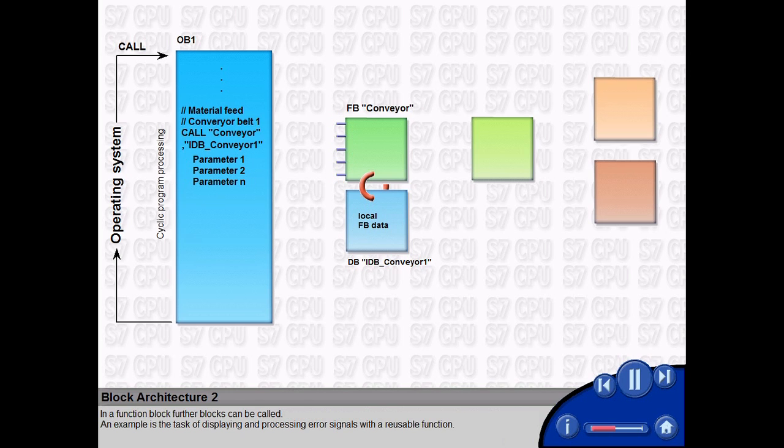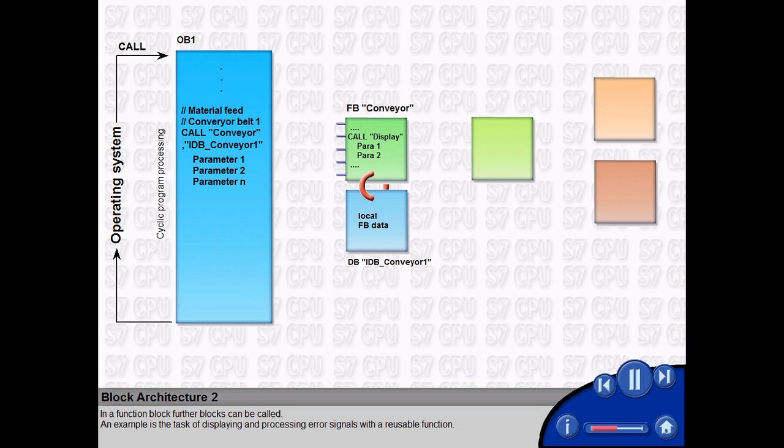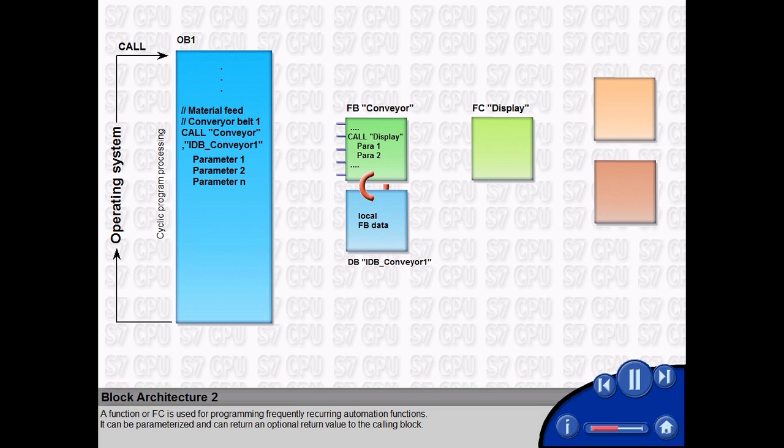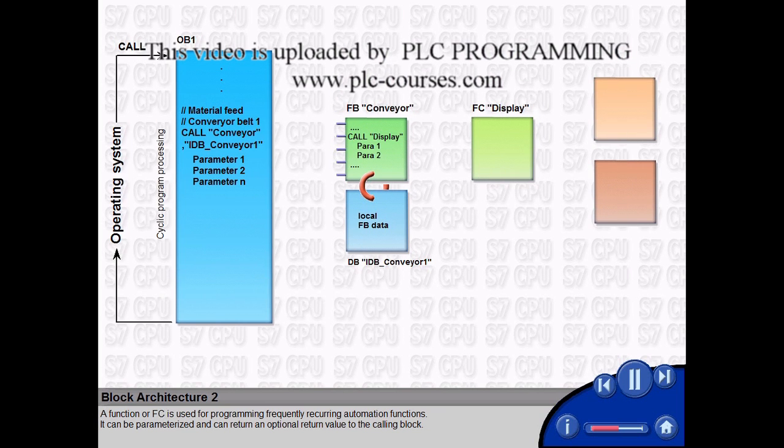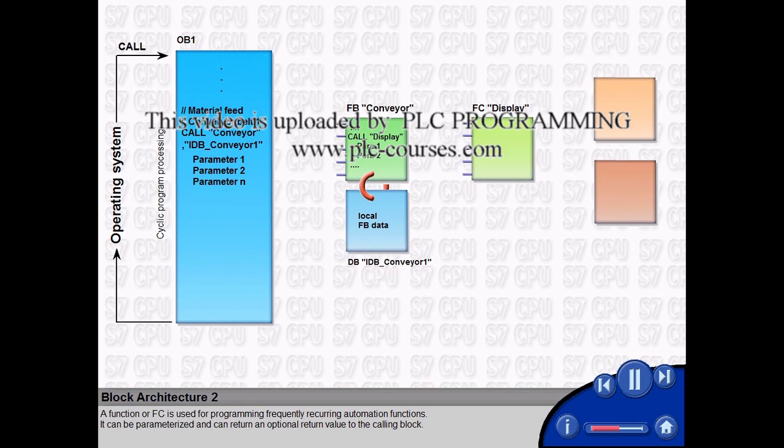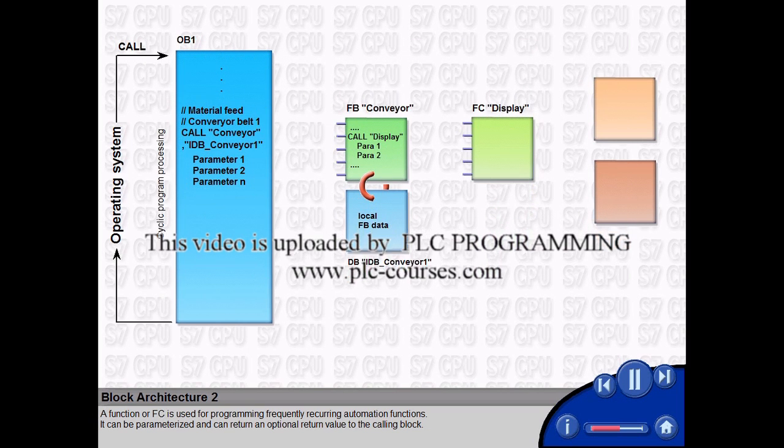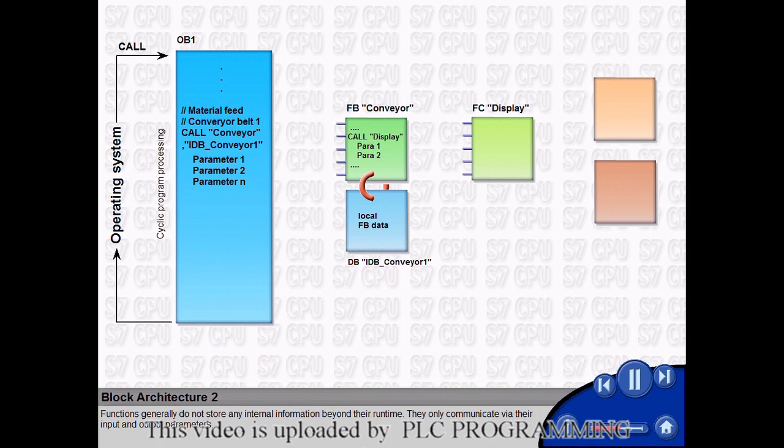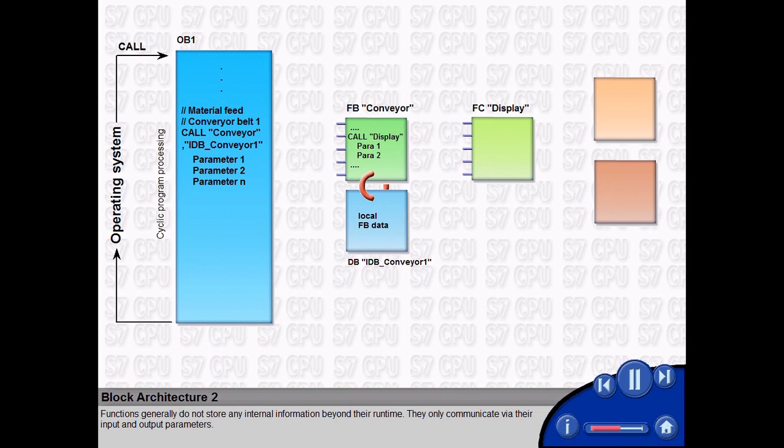In a function block, further blocks can be called. An example is the task of displaying and processing error signals with a reusable function. A function, or FC, is used for programming frequently recurring automation functions. It can be parameterized and can return an optional return value to the calling block. Functions generally do not store any internal information beyond their run time. They only communicate via their input and output parameters.